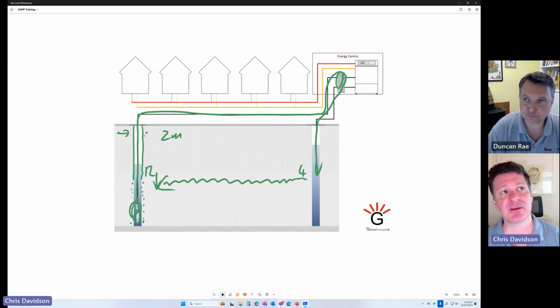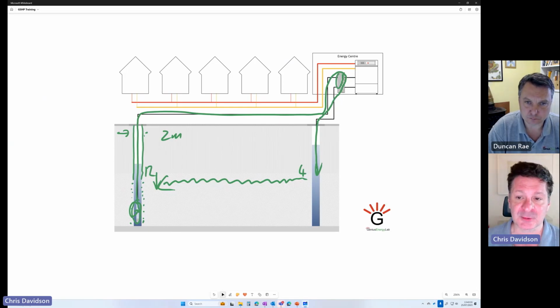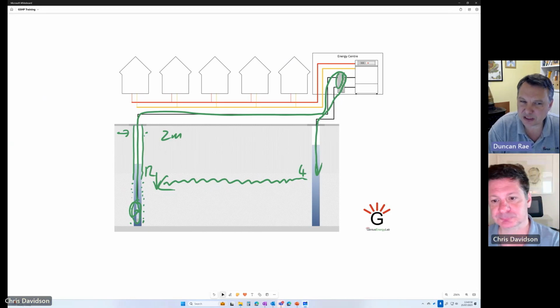Yes, there are. Most of the time when you're doing a surface water system and that body of water is not necessarily owned by the customer, or it's perhaps in contact with surface water, such as a river, there'll be a planning application required, and bodies, for example the Environment Agency, have the opportunity to contribute to that planning application. Generally speaking, it's not required for closed loop systems, but for open loop, there will be permitting and licensing required. I believe there is a planning application required if you're in a source protection zone 1 for closed loop. Yeah, it's a good point.